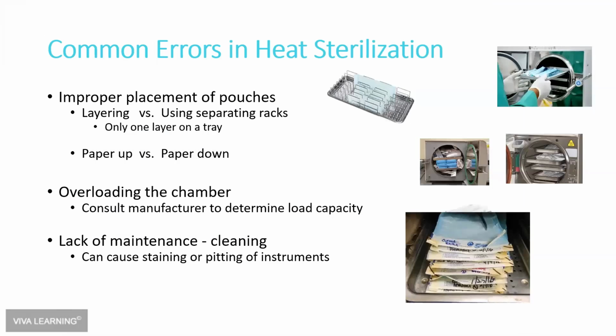So other errors we see in sterilization, and they're the most common causes of sterilizer failure. Layering them one on top of the other. That is not how they're meant to be put in sterilizers. These are labeled correctly. They're dated, and it's written on the paper part of the package. So that's a good thing. But it's possible that these packs in the center of that stack may not have been sterilized.